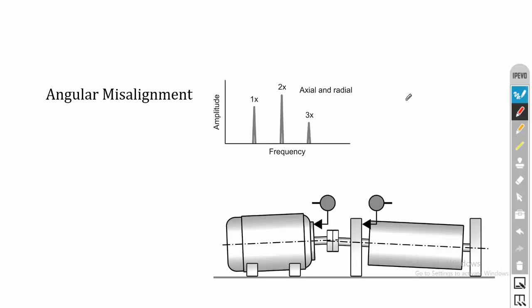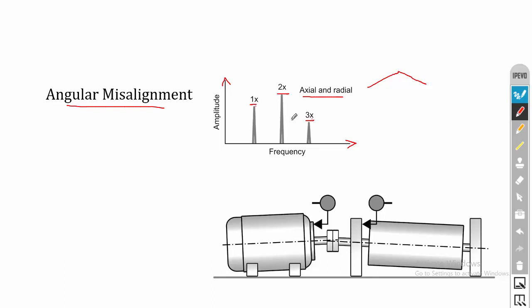The second type is angular misalignment, where the shafts are not collinear and are at an angle. In the case of angular misalignment, in both the axial and radial directions we get 1x, 2x, and 3x harmonics. The x-axis is frequency and y-axis is amplitude. For example, if the system runs at 100 RPM, you get peaks at 100, 200, and 300 RPM. So if it is parallel misalignment, you get 1x, 2x, 3x at radial direction; if angular misalignment, you get 1x, 2x, 3x at both axial and radial directions.